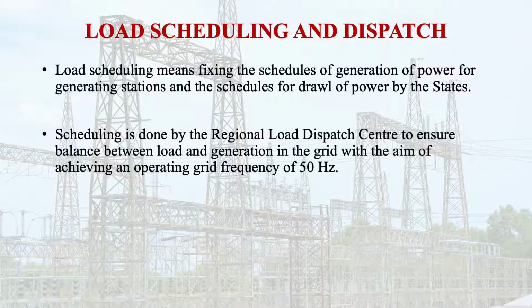Scheduling is done for the day ahead by the regional load dispatch center. I have already mentioned in my previous sessions that the load dispatch center is responsible for load scheduling and system operation. This is done to ensure balance between the load and generation in the grid, with the aim of achieving an operating grid frequency of 50 Hz for quality supply. Since power cannot be stored to a large extent, power generated has to be used at the instant of time. Therefore, it has to be ensured that generation matches the load at each point of time. This needs to be taken care of while load scheduling and load dispatching.